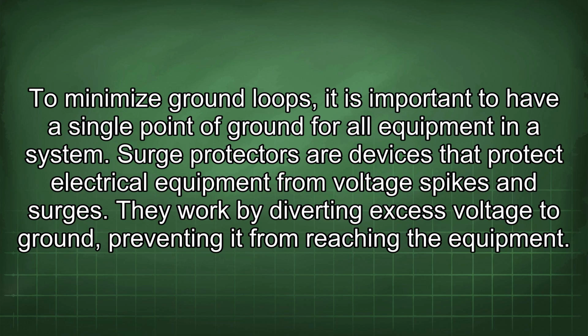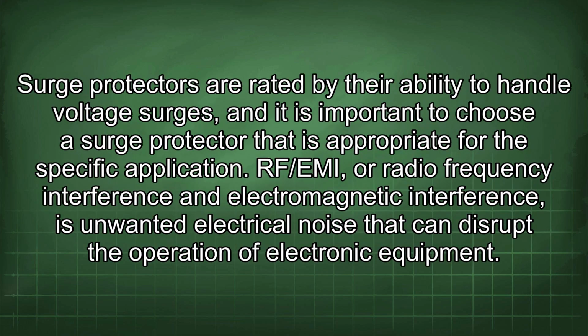Surge protectors are devices that protect electrical equipment from voltage spikes and surges. They work by diverting excess voltage to ground, preventing it from reaching the equipment. Surge protectors are rated by their ability to handle voltage surges, and it is important to choose a surge protector that is appropriate for the specific application.